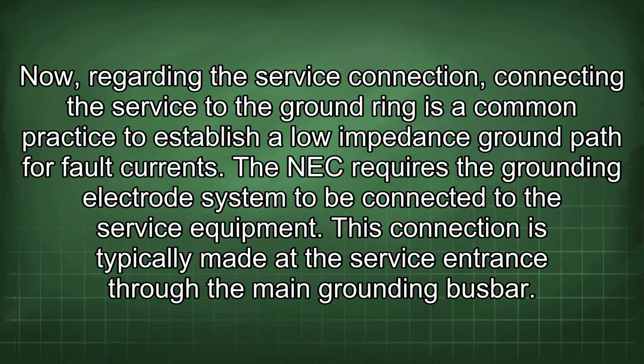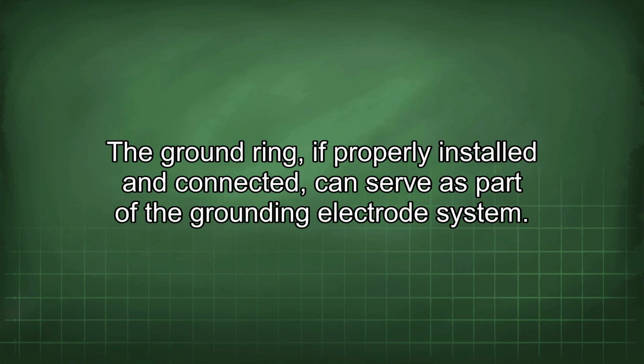Now, regarding the service connection, connecting the service to the ground ring is a common practice to establish a low impedance ground path for fault currents. The NEC requires the grounding electrode system to be connected to the service equipment. This connection is typically made at the service entrance through the main grounding bus bar. The ground ring, if properly installed and connected, can serve as part of the grounding electrode system.